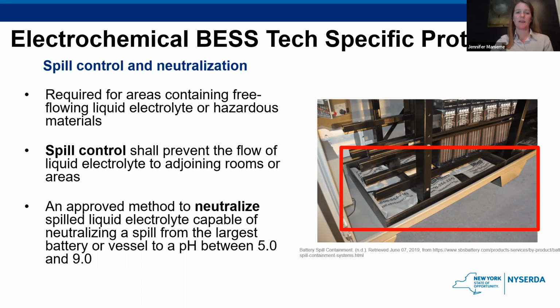For batteries that have liquid electrolytes, lithium ion not being one of them, but many of the other types do, they need to have some sort of spill control and neutralization. It needs to obviously prevent the flow of any spilled electrolyte from going to adjoining rooms or areas, and not just contain it, but also neutralize it to a pH between 5 and 9. Some of these systems can contain corrosives that can be up to, say, even like 1,000 gallons. So it's really important in the event of some sort of spill to be able to contain and neutralize it for everyone's safety.